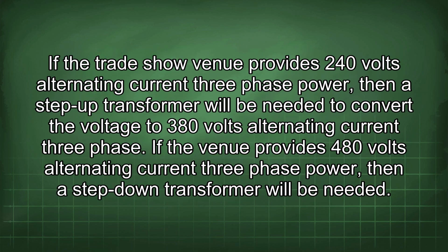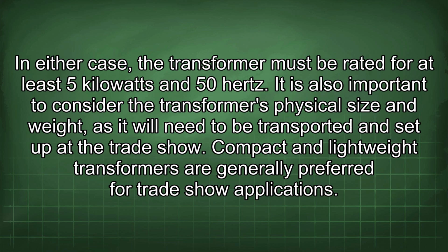If the trade show venue provides 240 volts alternating current 3-phase power, then a step-up transformer will be needed to convert the voltage to 380 volts alternating current 3-phase. If the venue provides 480 volts alternating current 3-phase power, then a step-down transformer will be needed. In either case, the transformer must be rated for at least 5 kilowatts and 50 Hz. It is also important to consider the transformer's physical size and weight, as it will need to be transported and set up at the trade show. Compact and lightweight transformers are generally preferred for trade show applications.